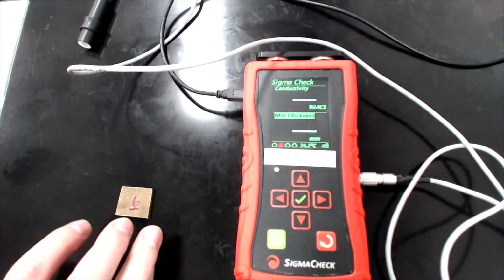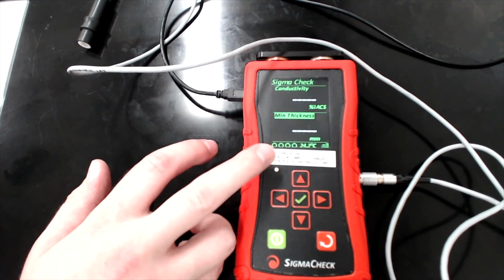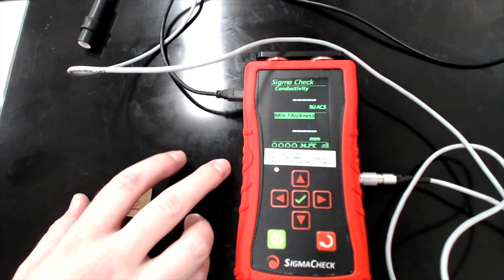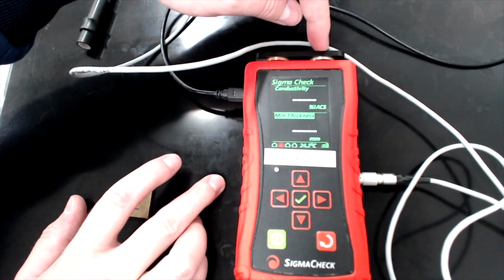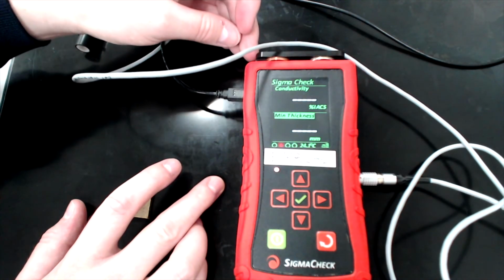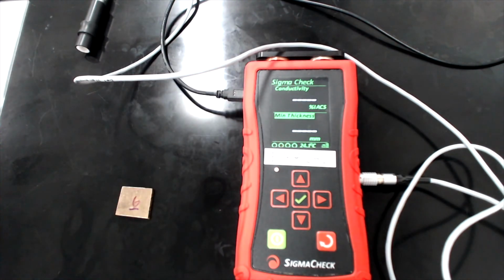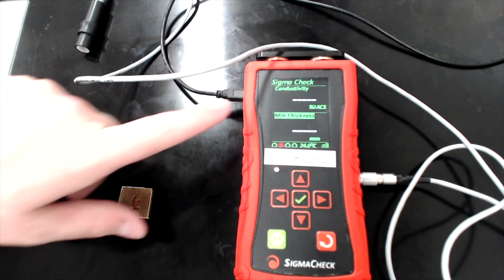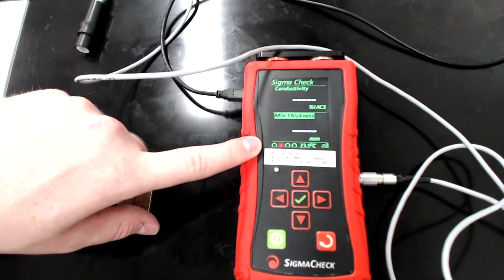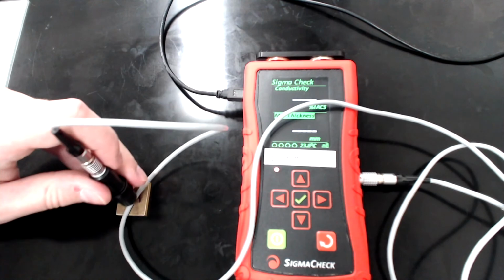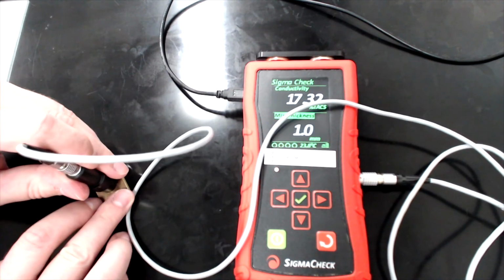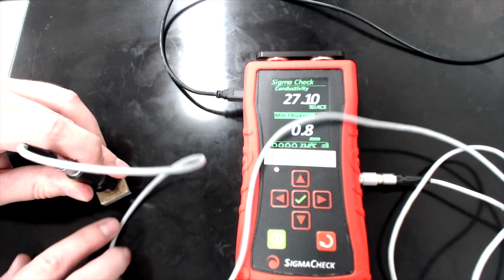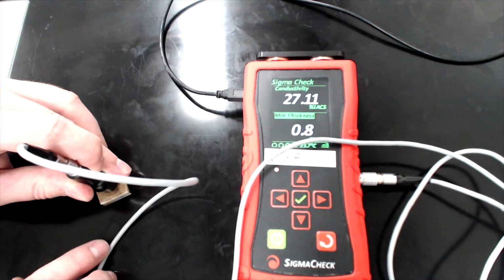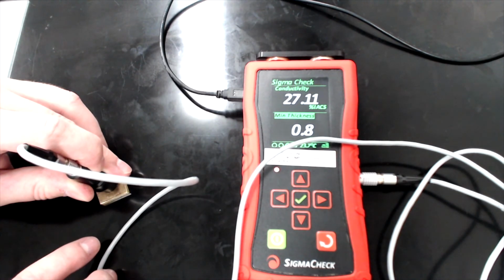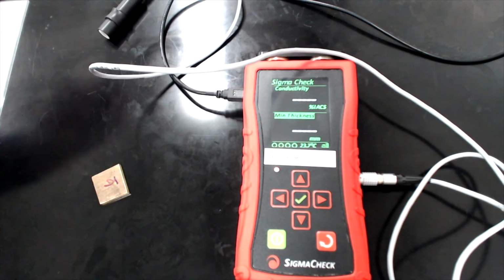Like I said, you want to make sure it's started. You want to make sure it can stabilize for 20 minutes before you do the calibration, and then do the calibration using our two standards located on the top. You can check throughout your measurements to make sure it's close to those calibrations. So I recommend checking the calibration before and after your measurements. And then once it's calibrated, and you're ready to go, you have the proper units and everything you saw from the settings, then all you have to do is take the probe and place it on the sample and make sure that it's resting flat and that you're not moving your hand or anything, and then you wait for it to stabilize and you record those values. So you want to get conductivity and then minimum thickness and liftoff. Those are the three quantities that we're going to be looking for.